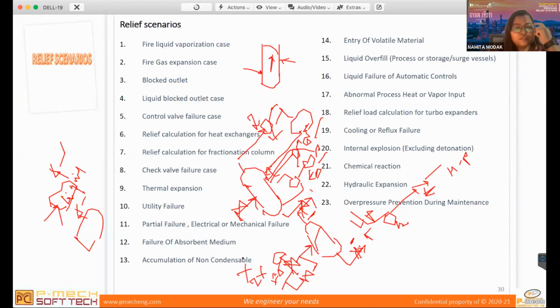Then accumulation of non-condensables. So let's say in this example, when you're cooling, this cooling water fails, or maybe an air cooler, if it is there. If your electric power fails, in that case your cooler is not working. So there is a lot of accumulation of non-condensables. So you have a lot of vapors here. So that also starts pressurizing your system. So that is the scenario.